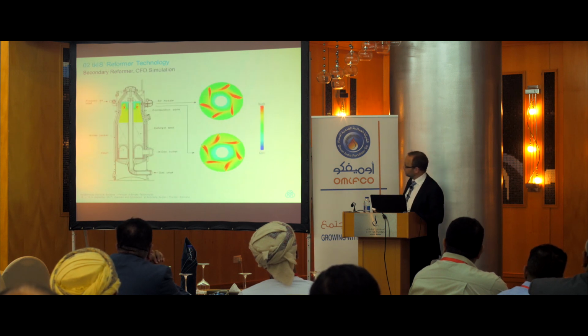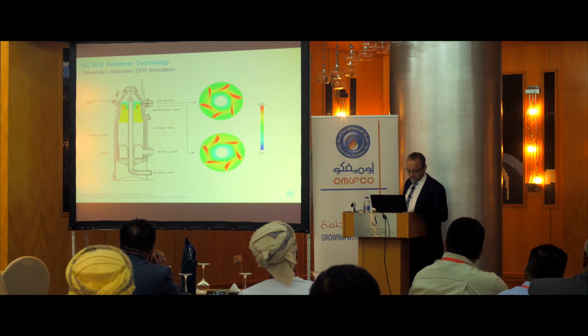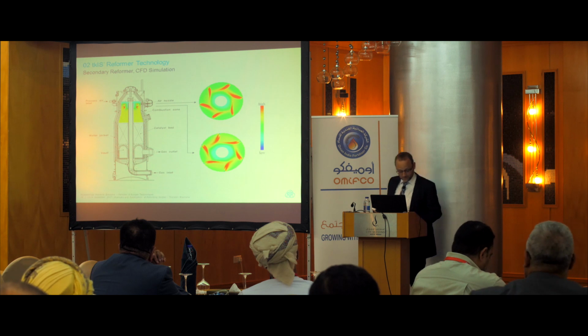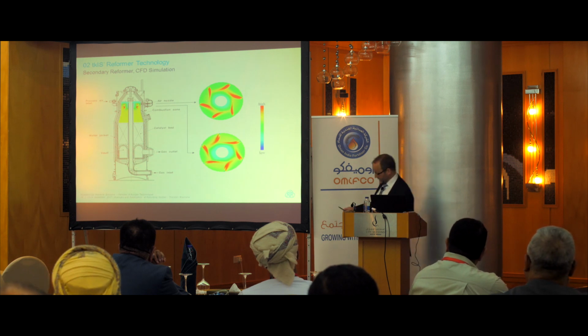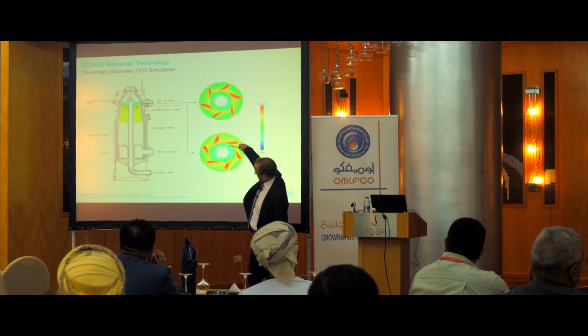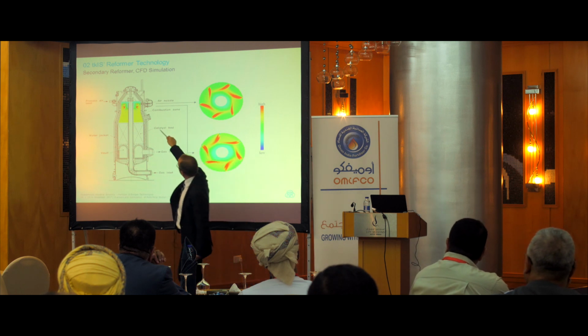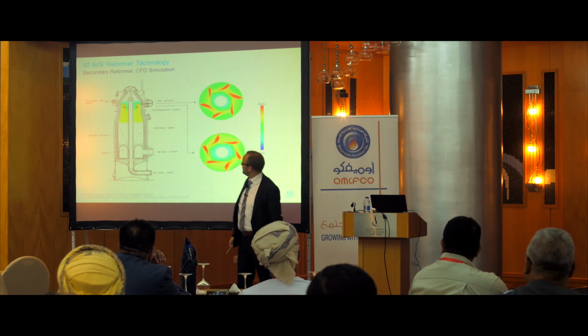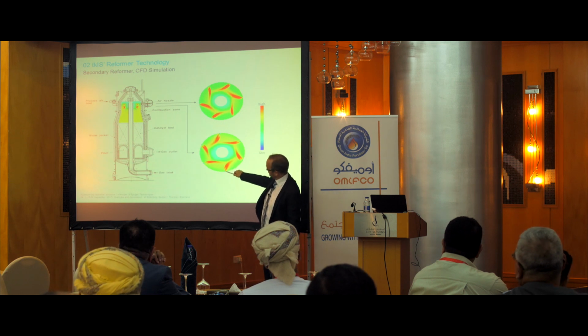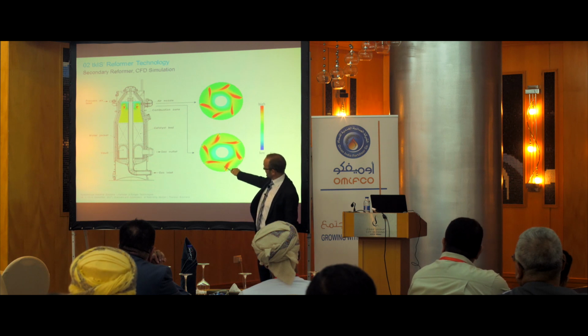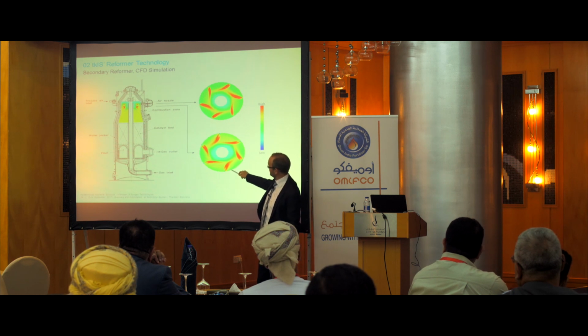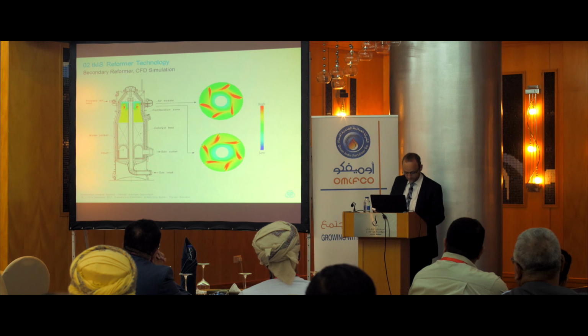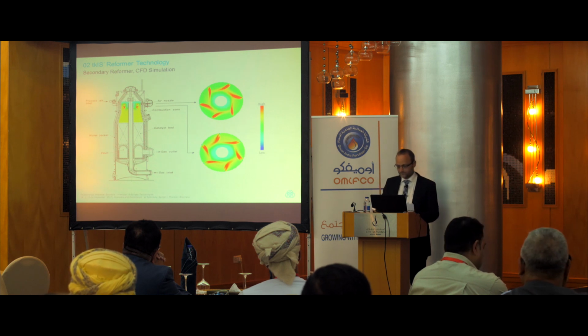Here you can see the before mentioned optimized burner design. The design of the combustion chamber has been optimized by CFD. The pictures here on the right are showing the temperature distribution at the different burner levels. And you can see that the design is optimized in such a way that the flames, or the oxidation, take place in the ring space between the riser pipe and the outside wall. So it's a kind of vortex created here.